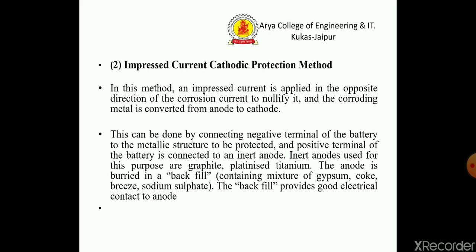The second method is impressed current cathodic protection. In this method, an impressed current is applied in the opposite direction of the corrosion current to nullify it, and the corroding metal is converted from anode to cathode. This can be done by connecting the negative terminal of the battery to the metallic structure to be protected.